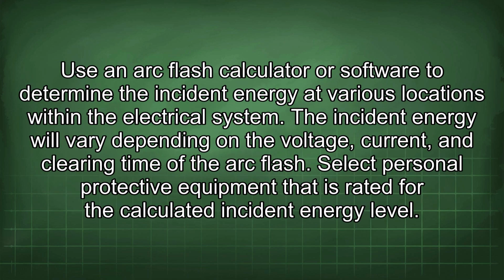Use an arc flash calculator or software to determine the incident energy at various locations within the electrical system. The incident energy will vary depending on the voltage, current, and clearing time of the arc flash. Select personal protective equipment that is rated for the calculated incident energy level.